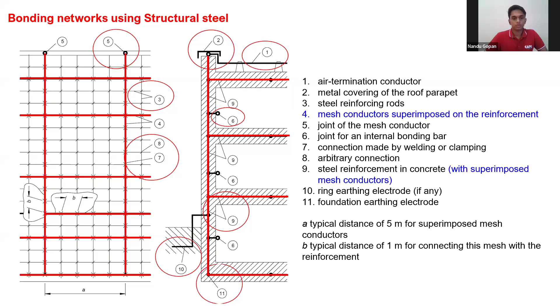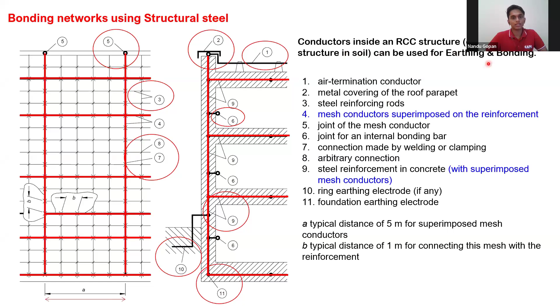So for bonding networks, you don't need to put in a separate bonding network. You can also use the RCC steel, but to reduce the potential difference, you might need to use superimposed mesh conductors, which can be 10 mm copper bonded steel, or you can use some stainless steel. It depends. So conductors inside an RCC can be used for earthing and bonding.